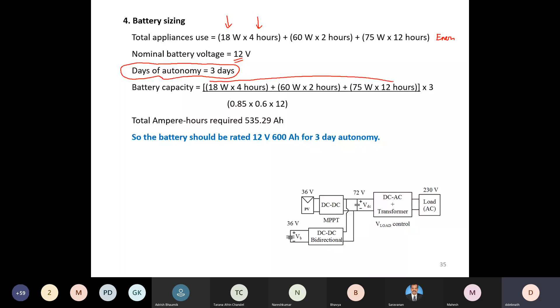So how do I do battery sizing? Using this formula: I take my energy requirement per day and multiply it by 3, which is the autonomy, then divide by battery voltage. This gives total energy, watt into time, or watt hour. Since watt hour is voltage into current, dividing VAH by battery voltage gives you the ampere hour rating.